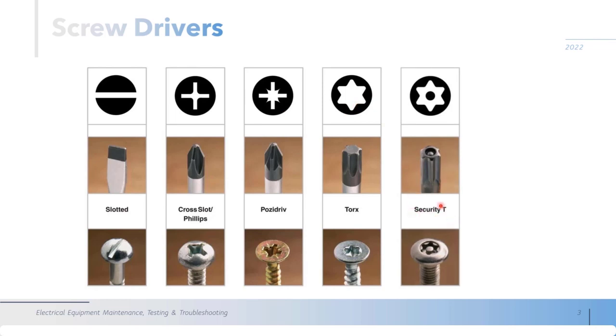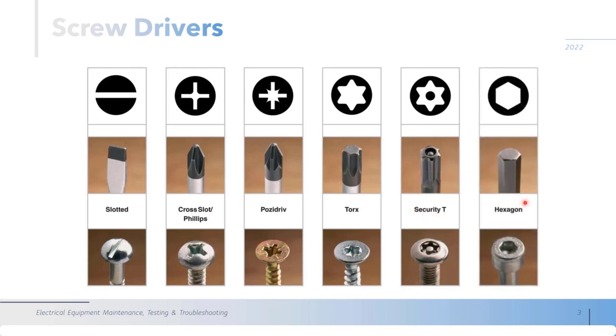Also, this is another type with a security feature, because this is a screwdriver that is not common in maintenance. So if you place some bolt like this, that will be something like a security bolt, and you cannot use these Torx because there is a surface area in the middle, so it will be in contact with this one, so these Torx will not work here. So you need the special Torx, and this is why we call this security, because this is not commonly used in industries. So the next one is this hexagon, and this is also used in motor terminals and switch gears. So you can see the face of this bolt, and this gives you a lot of torque also.